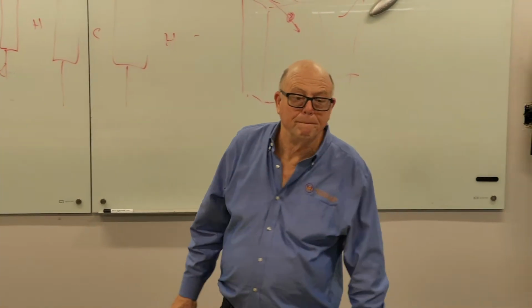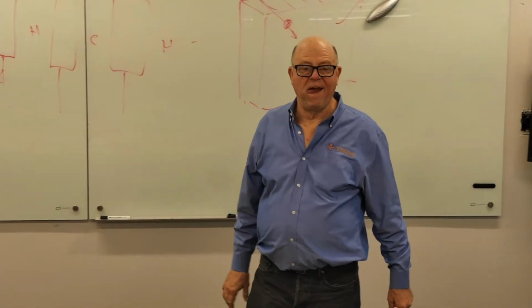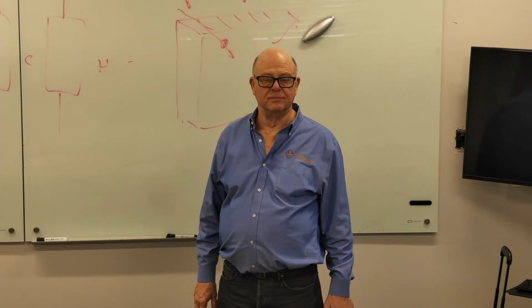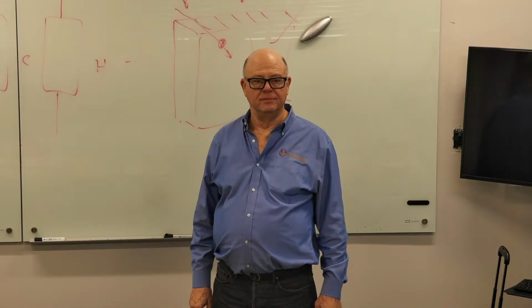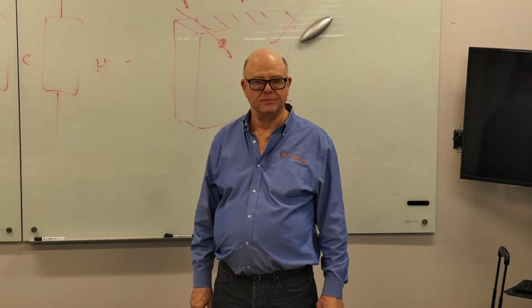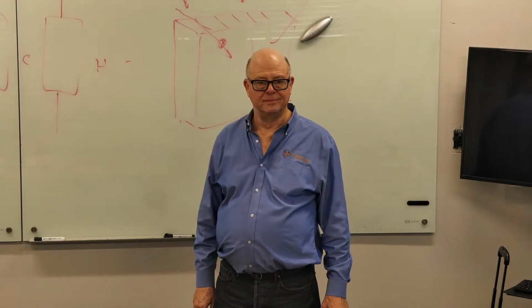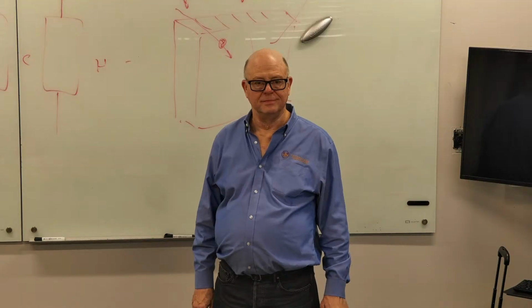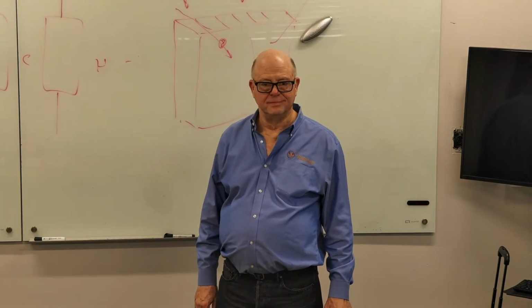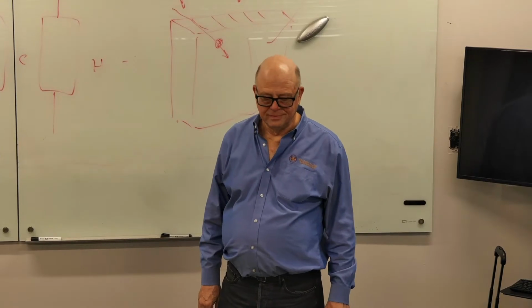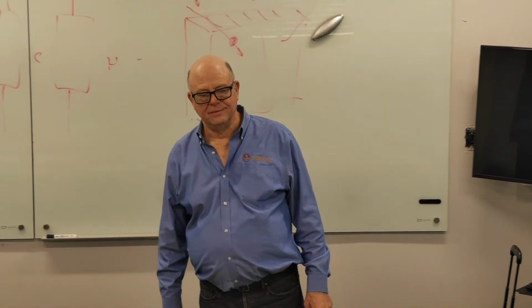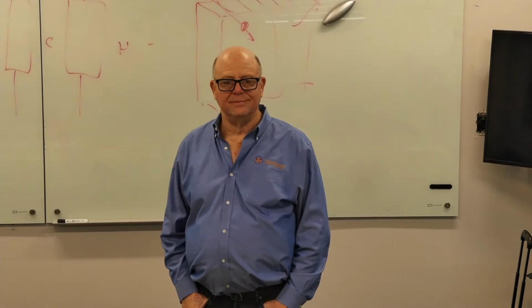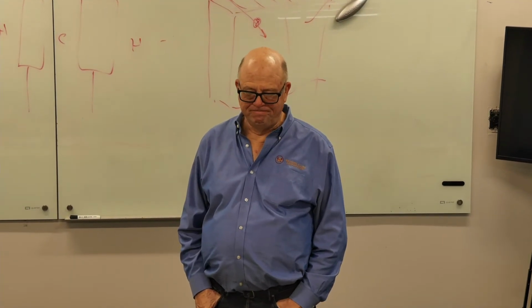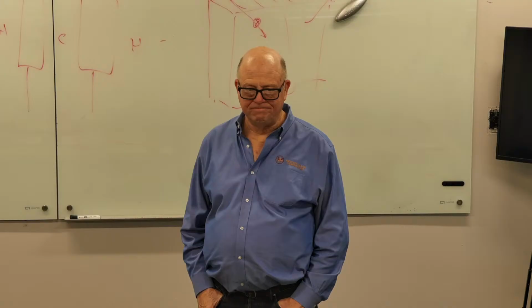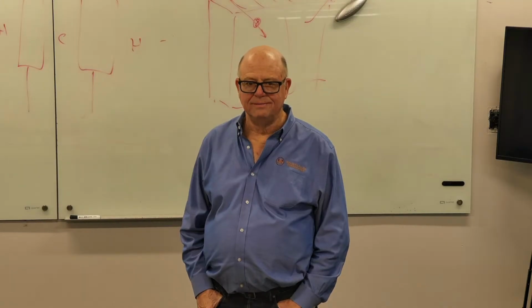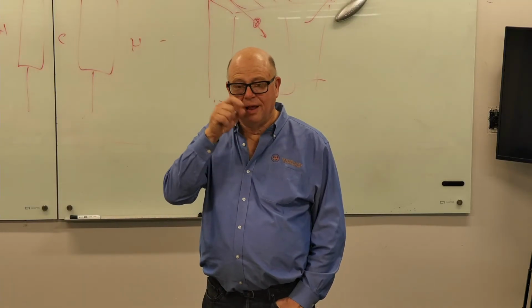So what ended up happening with that unit, because they didn't like serpentine, because it did have hot and cold, they were forced to run both units. And both units was way over capacity for that room. And it would short cycle basically, to the point where we got a call one time, the walls are sweating in the room. There was that much moisture because it wasn't running long enough to wring the moisture out. And when it cycled off, it would get redistributed back in the air.